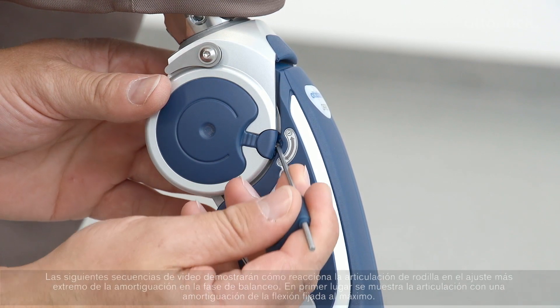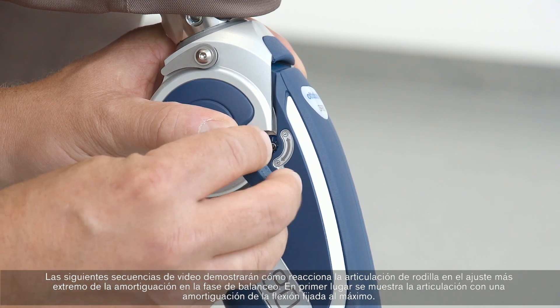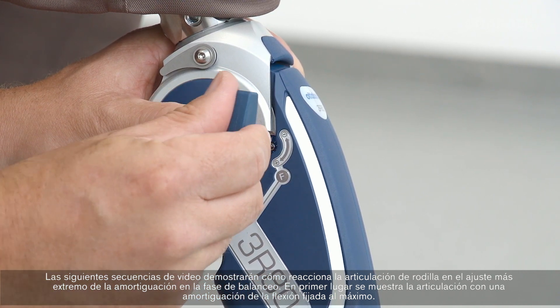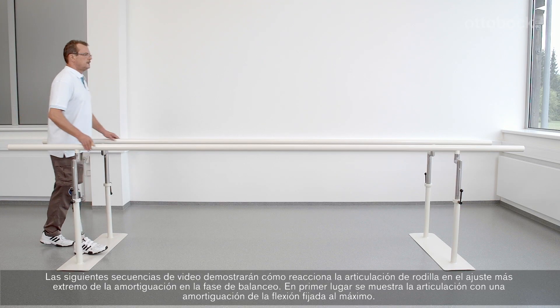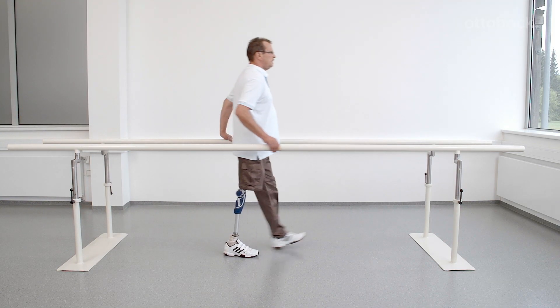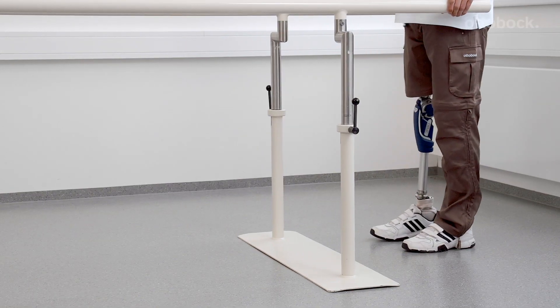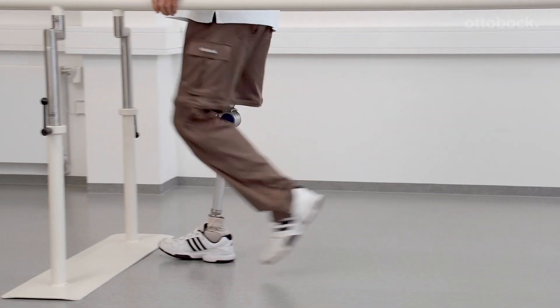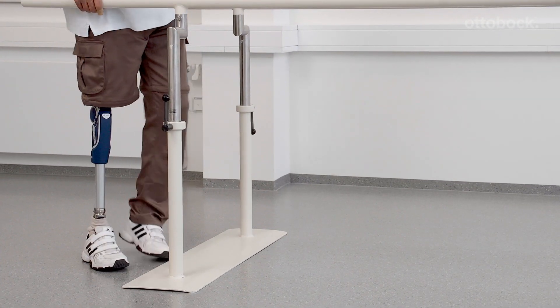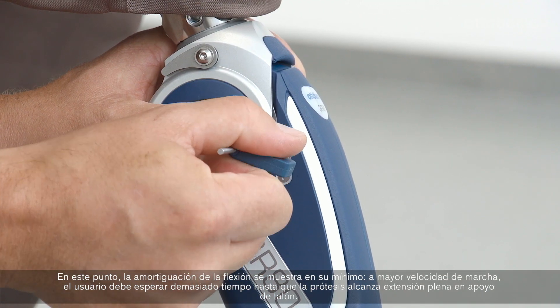The following video sequences demonstrate how the knee joint reacts at the extreme settings of the swing phase damping. First, the knee joint is shown with the flexion damping set at the maximum. The flexion damping is then shown at its minimum.